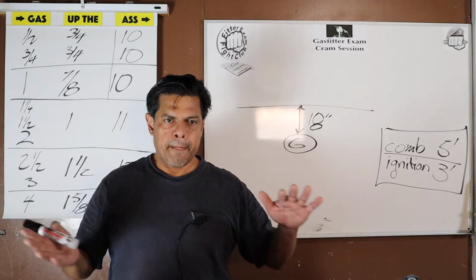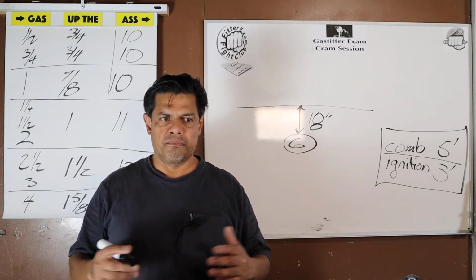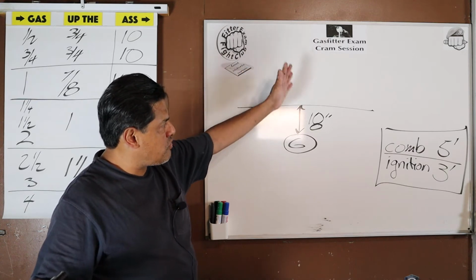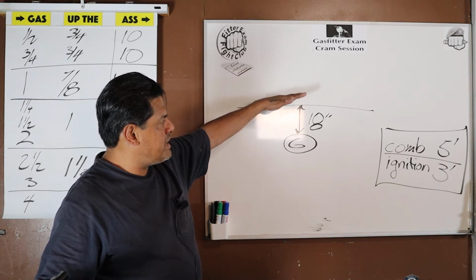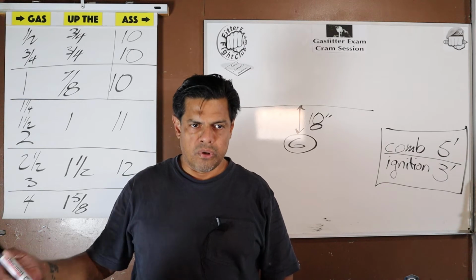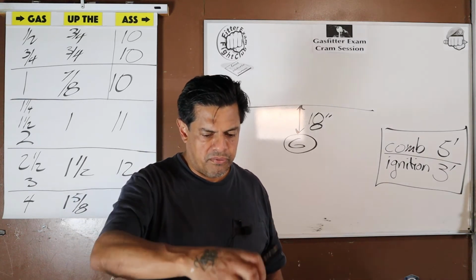You can imagine a driveway is generally going to be thinner. It's definitely going to be supporting a constant stress from vehicles over it. Vehicles are close to 2 tons. They're worried about that. The constant vehicles going back and forth over a driveway is going to produce too much of a load stress. So no driveways. As long as we're not dealing with a driveway and the piping is properly protected against other loads or freezing, you can go down to 18. You don't have to observe the blanket 24.